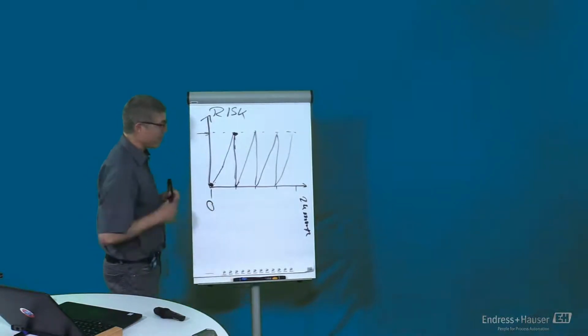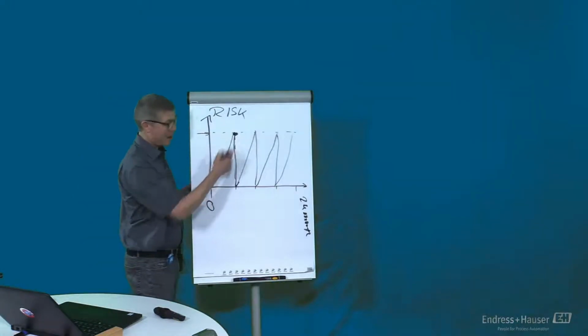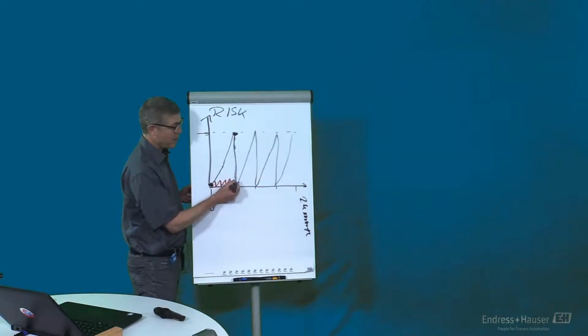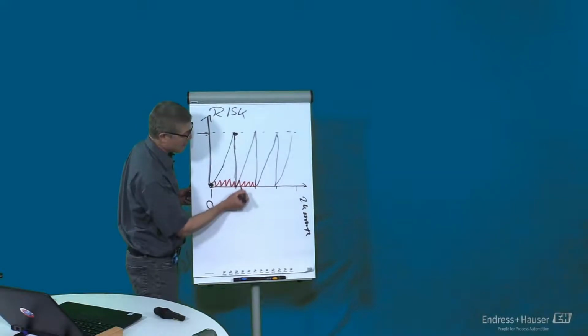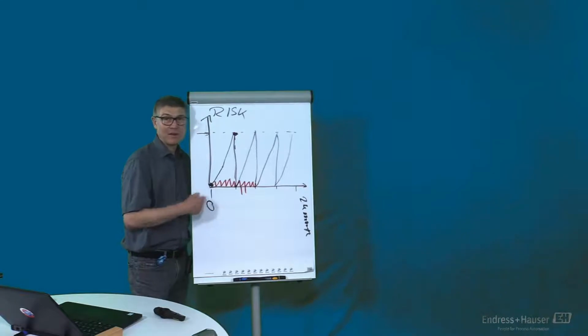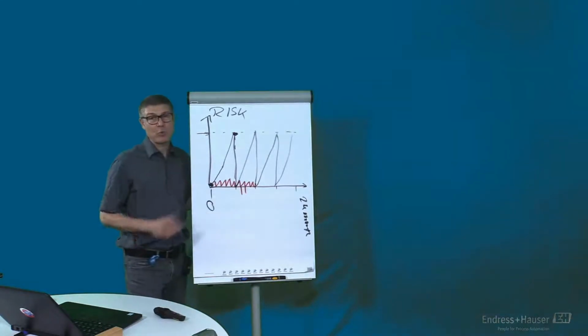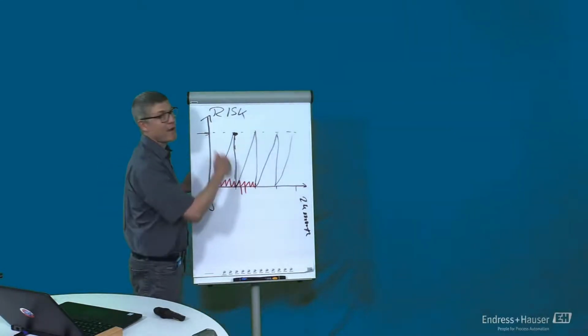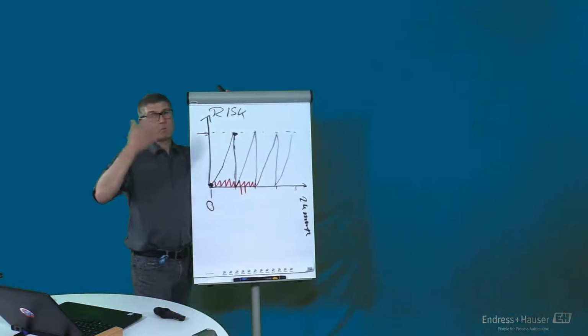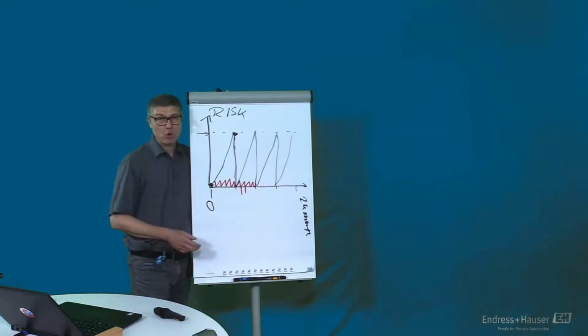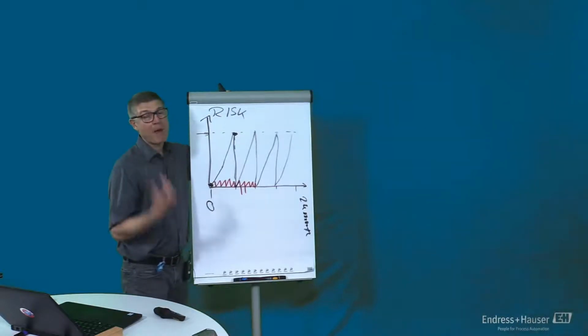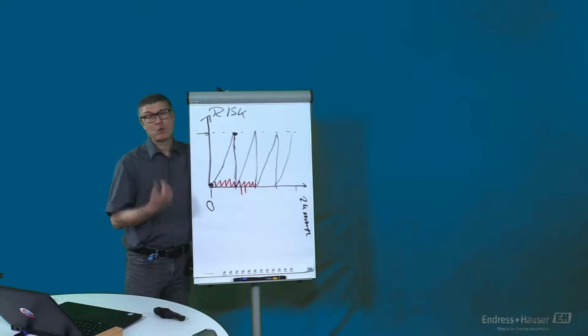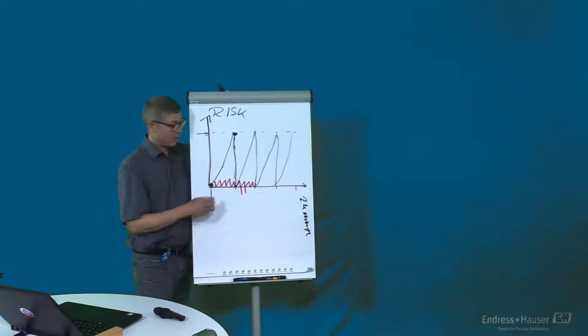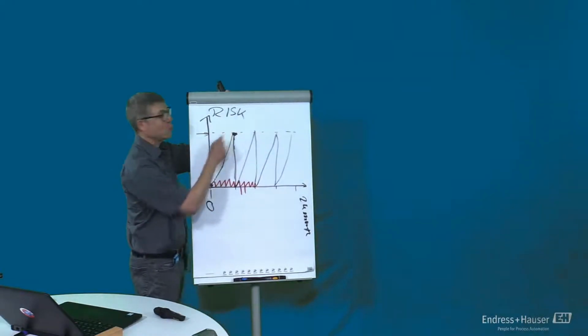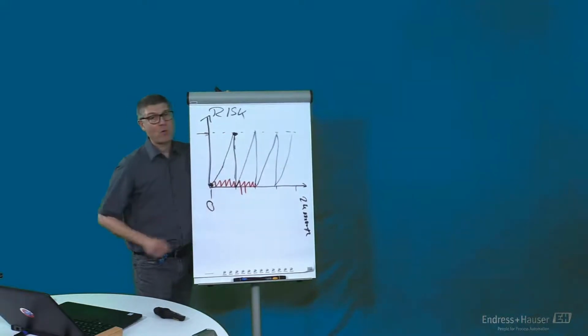Nobody knows. And the idea of the Trustsens is, if you do this calibration every time your process is heating up and cooling down, the maximum length of this uncertainty, whether the sensor was okay or not, is the time between two of these heating procedures. So instead of every 6 or 12 months, you do a calibration in milk applications once a day, in a medical autoclave 3 times a day, in biopharmaceutical plants every 1 or every 2 weeks, because this is the length of a batch. So it cannot happen any longer that you are totally surprised that your sensor was out of spec and you don't know since when. This is the general idea of this automatic calibration concept.